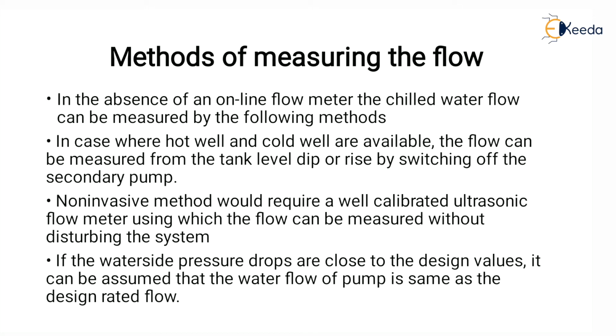Next is methods of measuring the flow. In absence of an online flow meter, the chilled water flow can be measured by the following methods. First, in case where hot well and cold well are available, the flow can be measured from tank level dip or rise by switching off the secondary pump. Next, a non-invasive method would require a well-calibrated ultrasonic flow meter, using which the flow can be measured without disturbing the system. And the last, if the water side pressure drops are close to the design value, it can be assumed that the water flow of the pump is the same as the design flow rate. So by these methods we can get the measurement of the flow.